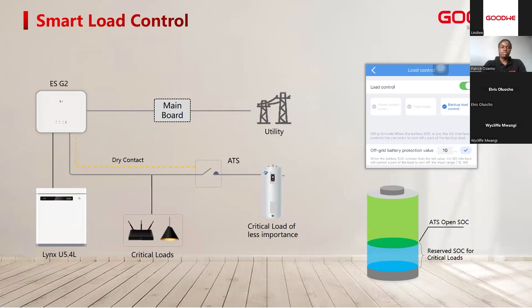So the 3 modes are actually critical in the ESG2 installation: power switching mode, which is manual, time mode, and the backup load control, which takes note of the battery SoC. Apart from that, GoodWe took note of microgrid systems. When you're installing the ESG2 inverter, you have an option of integrating the ESG2 with a generator. The generator can be switched on automatically from the ESG2. Either you can choose automatic switching of the generator via the internal relay switches of the inverter, or you can switch on the generator manually, and the inverter will work seamlessly with the generator to reduce your fuel consumption.